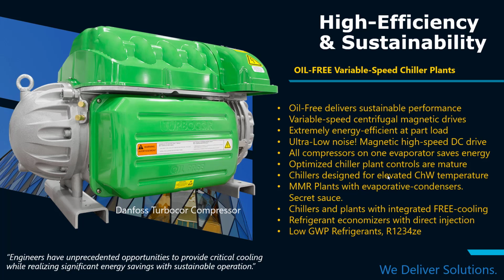Chillers are being designed now for elevated chill water temperatures. This is especially relevant for the data center world. Modular mechanical rooms with evaporative condensers are available. And quite frankly, that's a secret sauce in my view. When you marry an oil-free compressor at part load with evaporative condensing, you really do achieve the lowest total kilowatt usage. Chillers and plants with integrated free cooling are available. Refrigerant economizers with direct injection are available. There are low GWP refrigerants, including R1234ZE, available. Engineers have an unprecedented opportunity to provide critical cooling while realizing significant energy savings with sustainable operation.